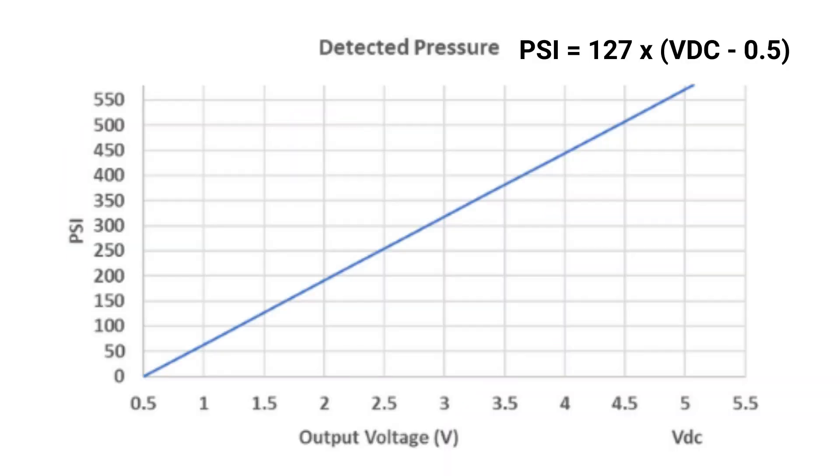Convert your pressure to DC voltage using the chart shown. For example, if you read 290 PSI, your output voltage should be 2.7 volts DC. Does your pressure correlate with your output voltage? If these values do not correlate, then you have a faulty transducer.